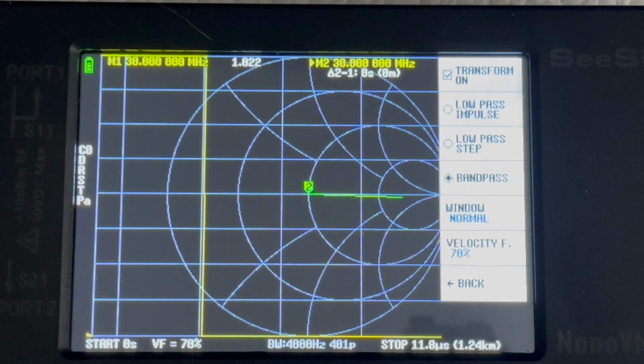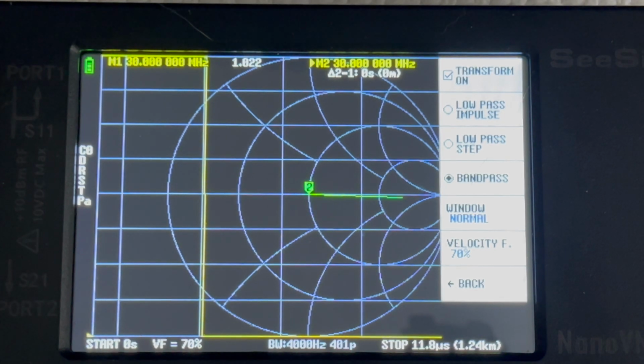Okay, yeah, I went and looked up the information, and I was correct. The start frequency must be set to 50 kilohertz, and the stop frequency must be set according to the distance to be measured. So it would change if I was, say, 300 feet of coax or 100 feet of coax, then the frequency would change, and I believe there's a formula for it. But I believe in my case, I'm usually not over 100, so one value will be close enough. But if the figures I get don't seem right, I can always change the frequency to find out. So it's a little bit of playing around at first.